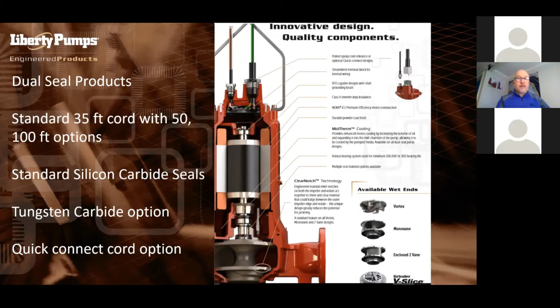All of the dual seal products are standard with a 35-foot cord, with 50-foot and 100-foot cord options also available. They have standard silicon carbide seals with a tungsten carbide option. Their standard is a potted epoxy cord entrance, but they also have the quick connect cord option, as you might be familiar with on the wholesale product—similar design, just a stainless steel nut versus plastic, heavier duty for heavier weights and things like that.